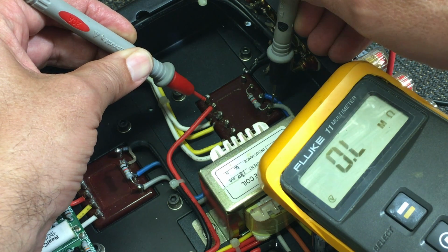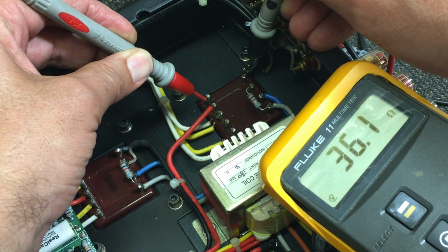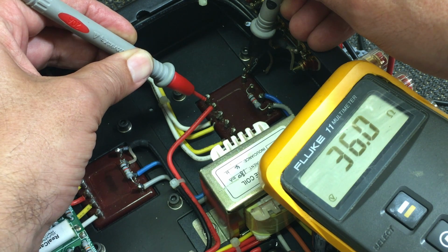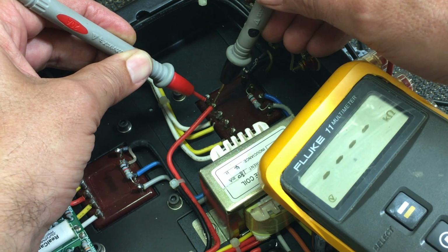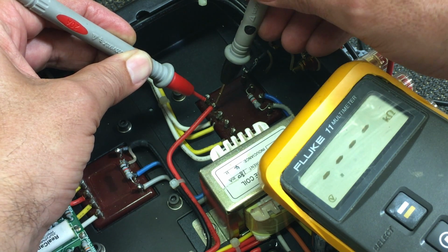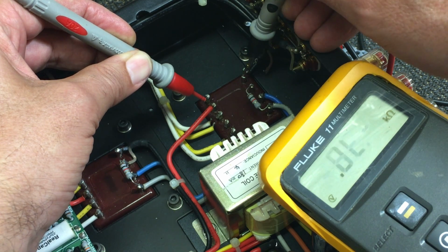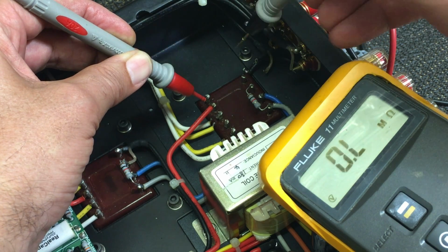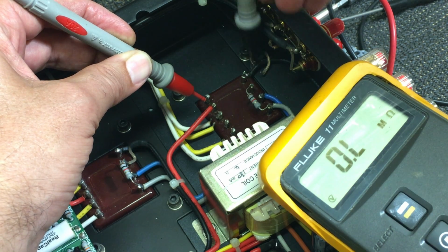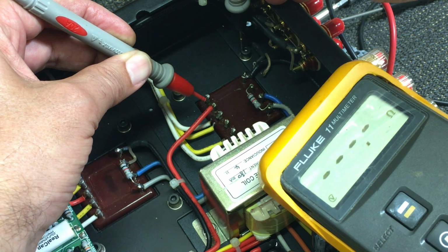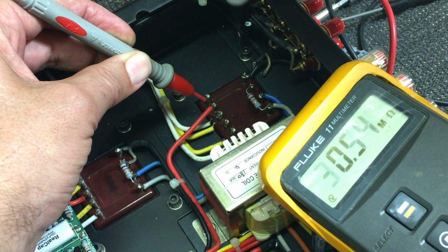Actually, that one or that one. So the short is actually not to the chassis or the leak - it's actually between this winding or this wire and one of the secondaries. So when you connect these two to ground, your short goes to ground. It's touching there now, see?